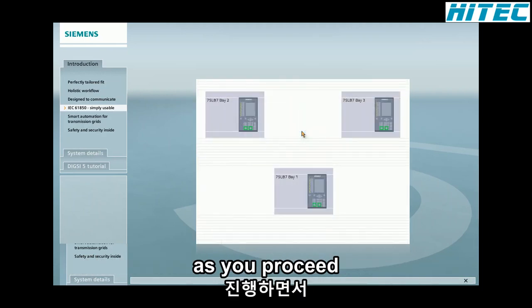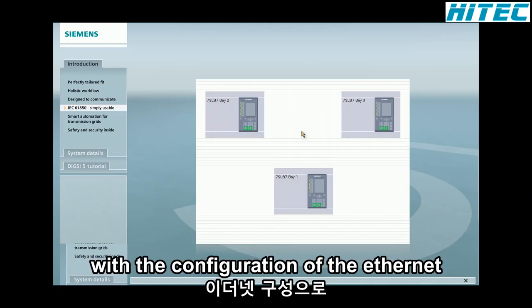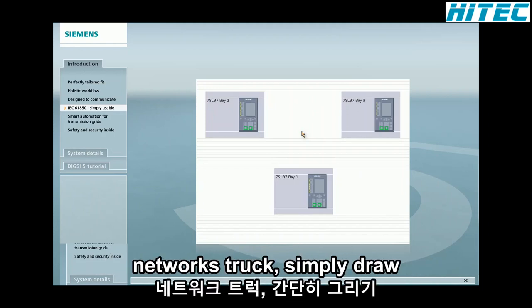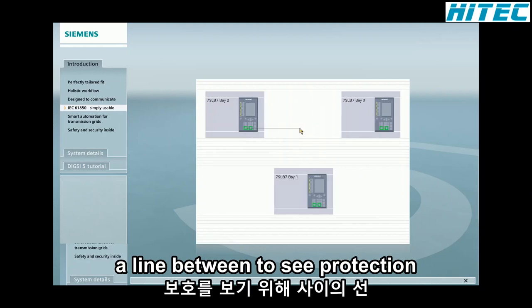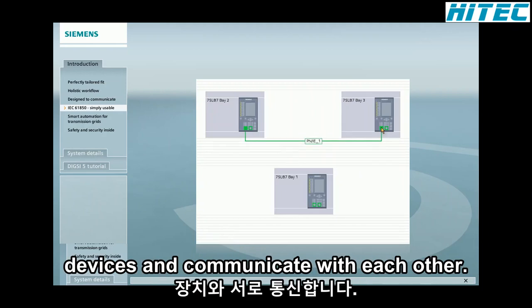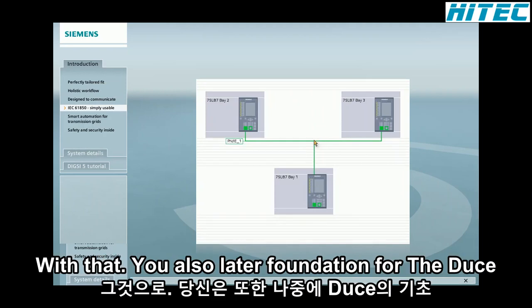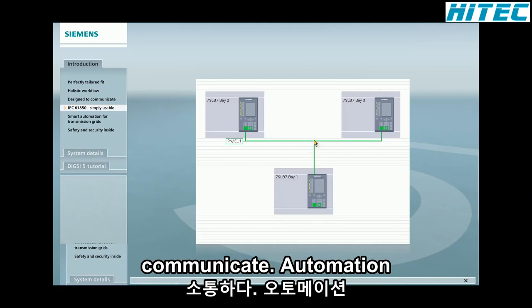Just as easily, you proceed with the configuration of the Ethernet network structure. Simply draw a line between 2 SIPROTEC 5 devices and DIGSI 5 immediately knows that these 2 devices are to communicate with each other in an IEC 61850 subnet. With that, you also lay the foundation for the GOOSE communication, that is, for the direct data exchange between the SIPROTEC 5 devices in the individual bays.